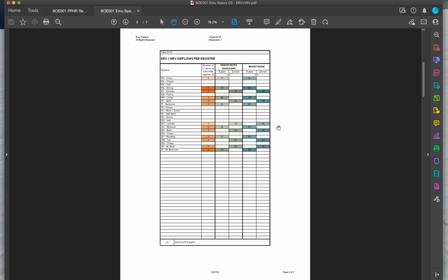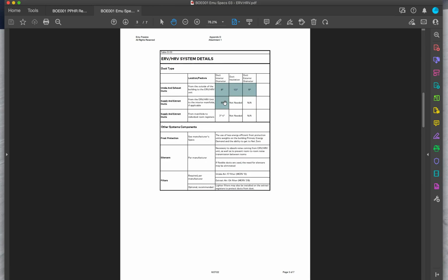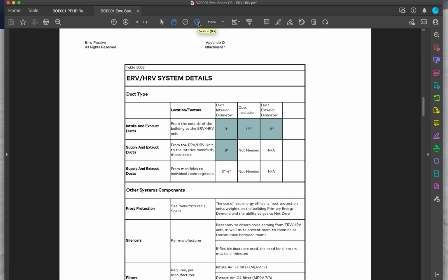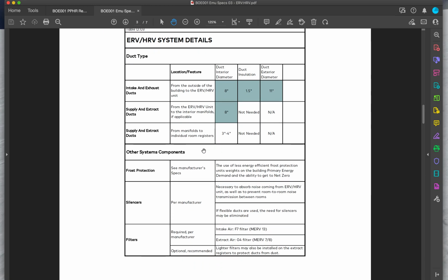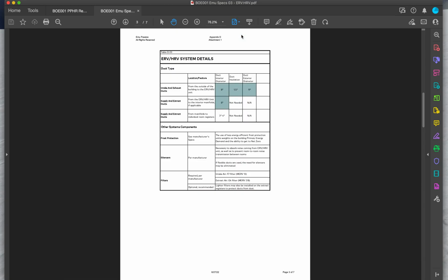You have the instruction in the document we just looked at. Then other indications as far as ductwork, need for insulation, silencers, frost protection, something that is climate specific. In my case, it's very cold, so I do need frost protection. And then types of filters to block off pollution from the outside. So a higher filtration rate on the air that comes in from the outside, the intake, compared to a lower filtration rate on the air that comes from inside the house into the ERV. Something that we cover in class quite a bit.